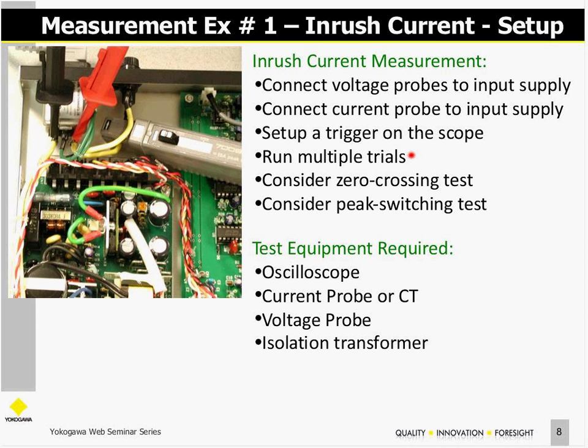We may want to run several trials of this, because in-rush current depends on the state of the input capacitor of your input rectifier capacitor filter circuit. If that capacitor has a little bit of charge on it, you won't have as much in-rush current. Also, the in-rush current depends on whether your power supply turned on during the zero crossing or during the peak. Your 120 volts RMS mains may be at a peak voltage at the very instant you apply voltage to your switch mode power supply.